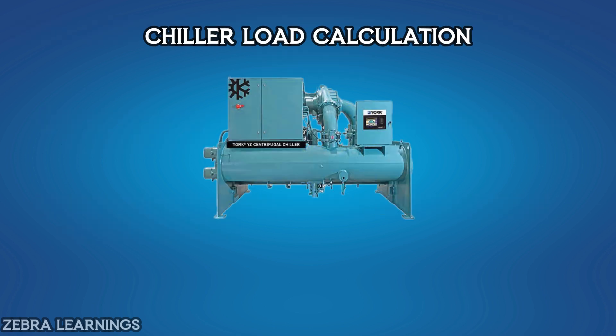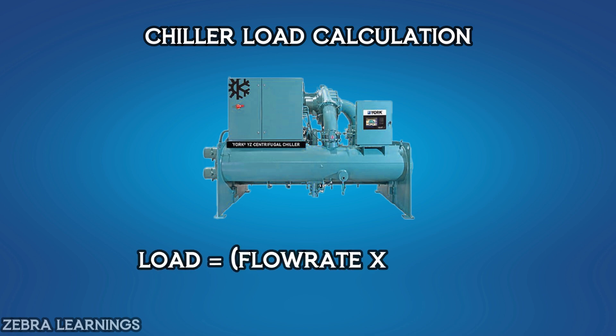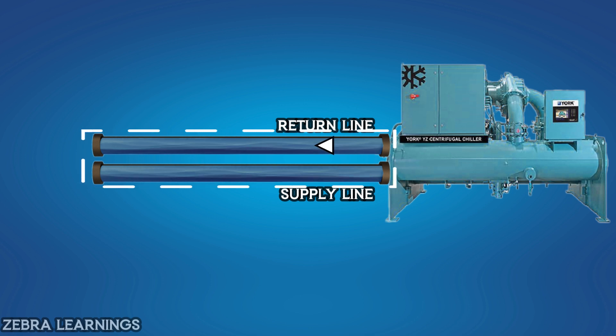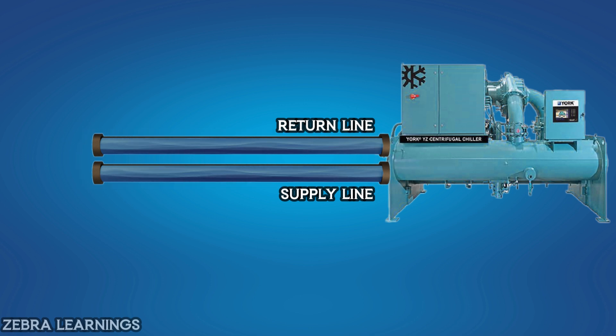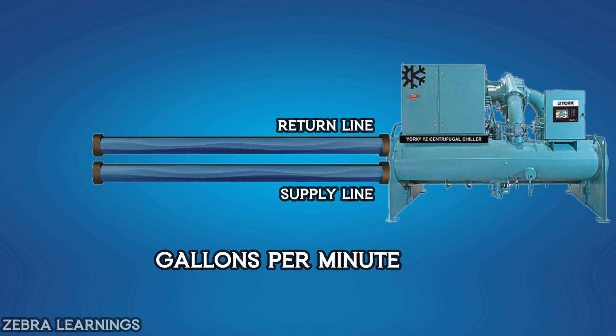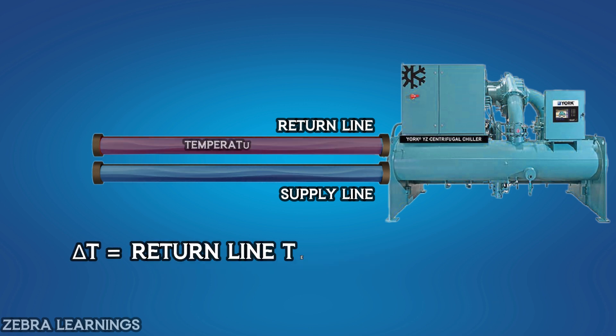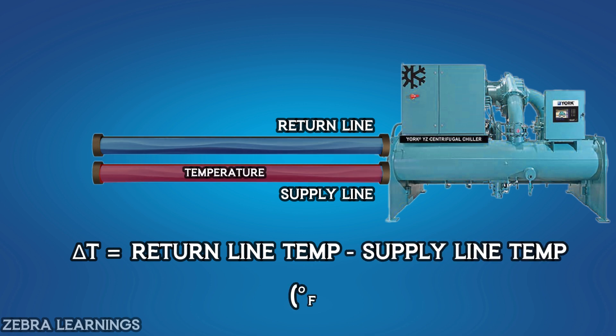Now let's learn how to calculate load. The formula to calculate chiller load is: Load equals flow rate multiplied by delta T, divided by 24. Flow rate is the measurement of how much water is flowing through the chilled water pipeline, measured in gallons per minute. Delta T is the difference between the return line water temperature and the supply line water temperature, measured in degrees Fahrenheit.